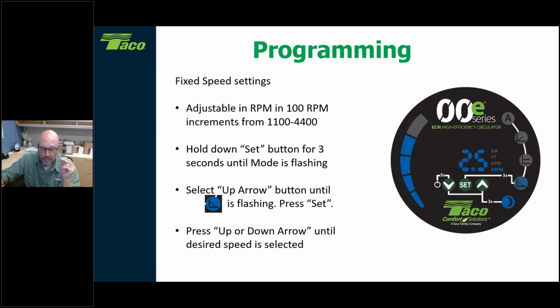And this is very critical. Press set again, because if you do not hit that set button, it will go back to the default RPM it was sitting at. Right now that would stay at 2,500 RPM, and if you needed it to run at 4400, it's going to go back to that. So remember, hit set again, because if you don't hit anything, it just sits there and eventually goes out of programming mode. It's back into run mode because nothing was saved. Hitting set saves it in that RPM mode.